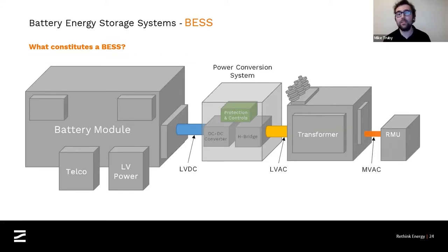We then have some kind of low voltage DC link into a power conversion system. This will typically be at around 1000 volts DC. Some are a little higher, some are a little lower. It depends on the system. The power conversion system is then one of the most critical parts of the whole system. So it'll be typically called a battery inverter. Now, I appreciate that in traditional systems, an inverter is a DC to AC conversion system, but a battery inverter must be, by definition, a bi-directional system. We have to be able to both charge and discharge.